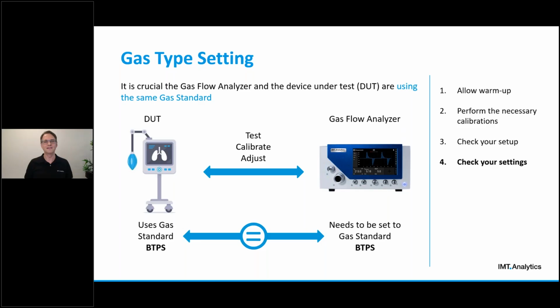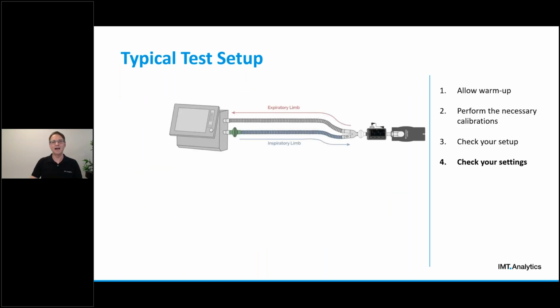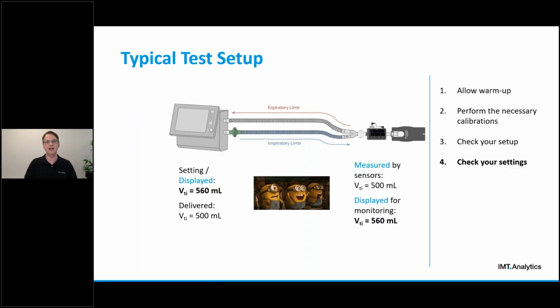Most manufacturers specify the gas standard in their technical documentation, maybe the service manual or user manual. Otherwise, they will be able to tell you when you ask them, or maybe you hear it when you go through service training. Okay, back to our example. If we have the gas standard on our gas flow analyzer matching the one used by the ventilator, the displayed volumes should then match, as we are now comparing apples with apples, or in these guys' case, maybe more banana with banana. All right, before we talk about the next important settings, let's quickly recap the most important takeaways. Number one is to make sure that you set the gas type on your analyzer to the gas you're actually measuring. And number two is to set the gas standard on your gas flow analyzer to the same one used by your device under test.